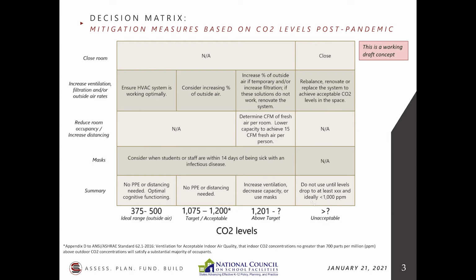This is a point of contention. I wouldn't say contention, but controversy. You can open windows, okay? Well, there are a lot of points related to opening windows. So what do you do there? Say you open a window and you do have some sort of mechanical system, and you're bringing in some degree of outdoor air, you may actually, in many schools, be pressurizing the building. If you open a window, you're simply disrupting the mechanical system. You're disrupting the ability of the system to control temperature. And I'm not saying not to do this. I'm just saying that there is no assurance you're going to get more outdoor air in that situation.